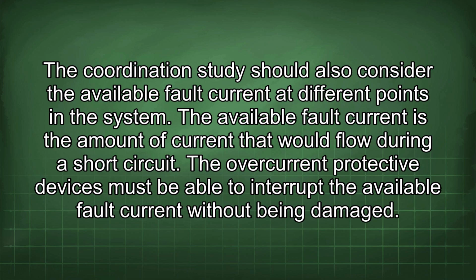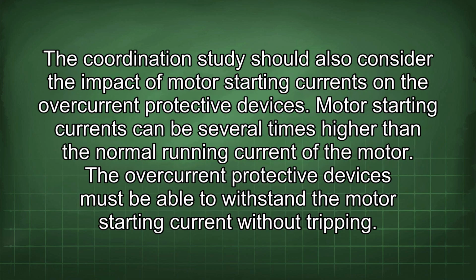The coordination study should also consider the available fault current at different points in the system. The available fault current is the amount of current that would flow during a short circuit. The overcurrent protective devices must be able to interrupt the available fault current without being damaged. The coordination study should also consider the impact of motor starting currents on the overcurrent protective devices. Motor starting currents can be several times higher than the normal running current of the motor. The overcurrent protective devices must be able to withstand the motor starting current without tripping.